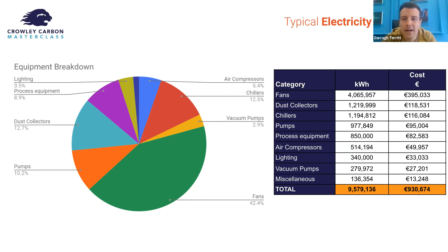Typical electricity consumption - what you can see on the screen is a typical energy breakdown on a pharmaceuticals plant, albeit different plants with different processes will have slightly different breakdowns. It's not a one-size-fits-all representation, but it is reflective of the utilities used from an electrical standpoint. HVAC typically represents anywhere between 50 and 75%, which encompasses all of those services feeding into the HVAC. We'll be going through various measures that can be allocated to reduce consumption in both electricity and thermal, that usually generate savings anywhere between 5 and 35%. Obviously this is dependent on site conditions and whatnot.